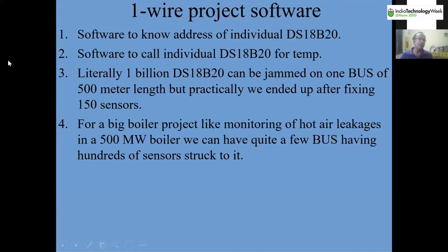The second software we have provided works like this: after knowing the address of all these 100 or 50 sensors, we put those addresses in the second software and call the temperatures by those addresses, which makes it very easy. We put it in an array in the program, putting all the addresses in an array and calling them by array elements, 1 to 50. So here we have put 150 sensors, then 100, 150 in another project.